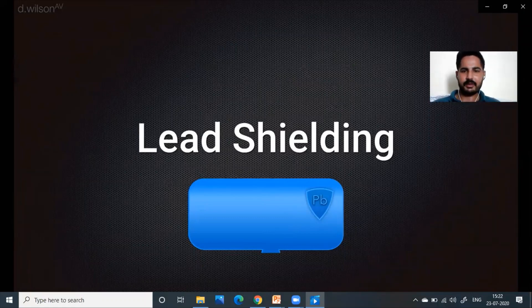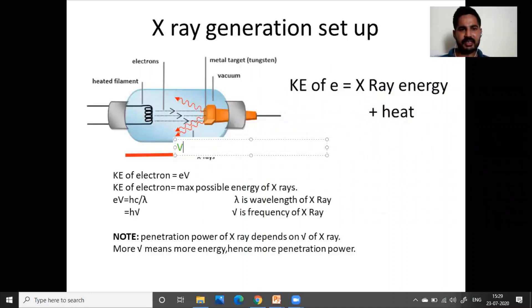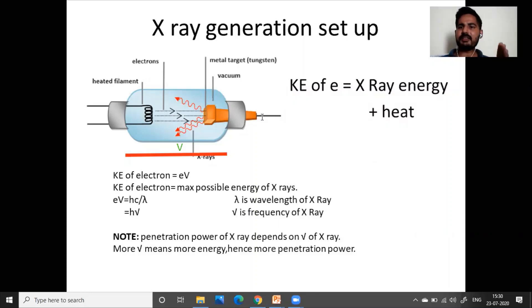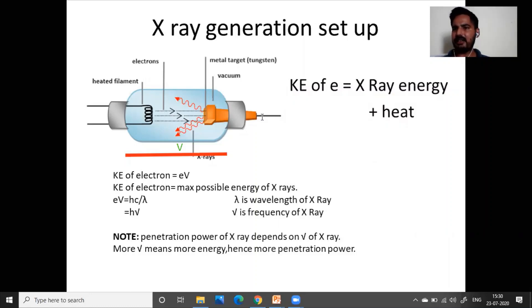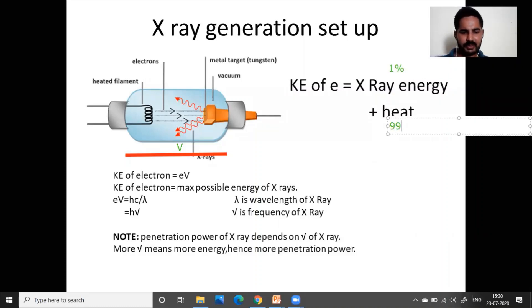For example, if we want to take an x-ray of a patient, we allow x-rays only to come in that direction towards the patient. The potential difference V provided across the tube gives the electron its kinetic energy: kinetic energy of electron equals charge of electron times potential difference V. When electrons hit the target, this is converted into x-ray radiation energy plus heat — approximately only 1% is converted into x-rays and approximately 99% is converted into heat.